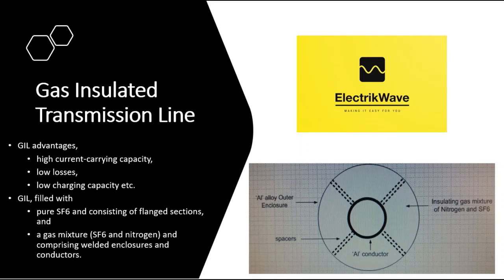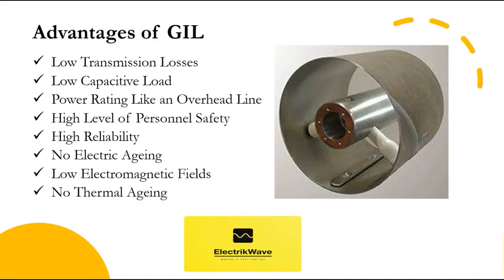GIL solutions offer different advantages such as high current carrying capacity, low losses, and low charging capacity. The first generation of GIL was filled with pure SF6 and consisting of flanged sections, and the second generation of GIL was filled with a gas mixture of SF6 and nitrogen, comprising welded enclosures and conductors. GIL offers several advantages: low transmission losses, low capacitive load, power rating like an overhead line, high level of personnel safety, high reliability, no electric aging, low electromagnetic fields, and no thermal aging. Now let's understand each advantage one by one.